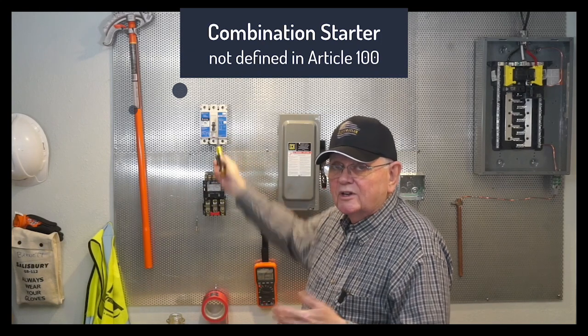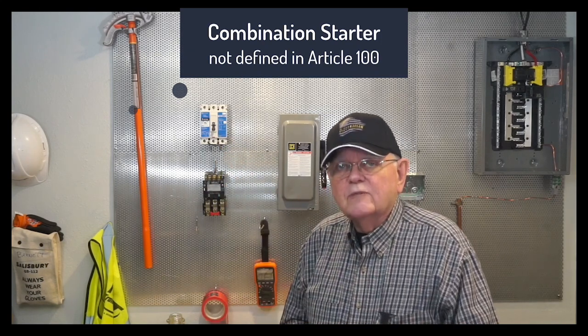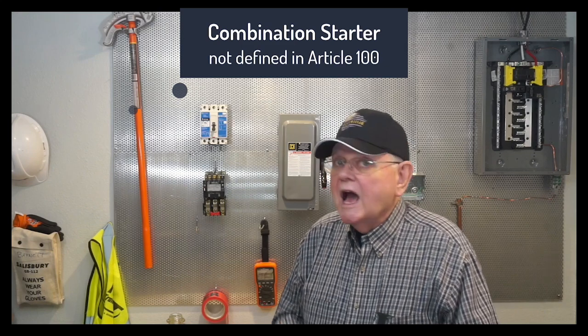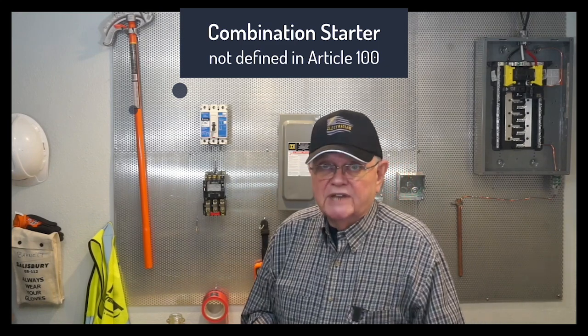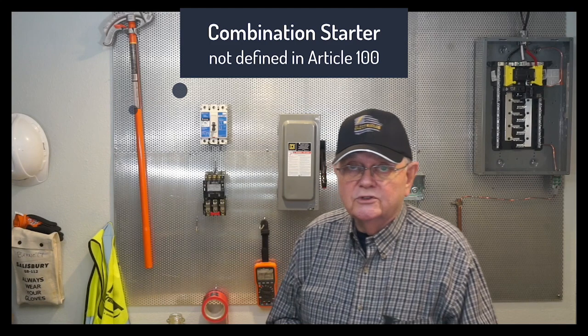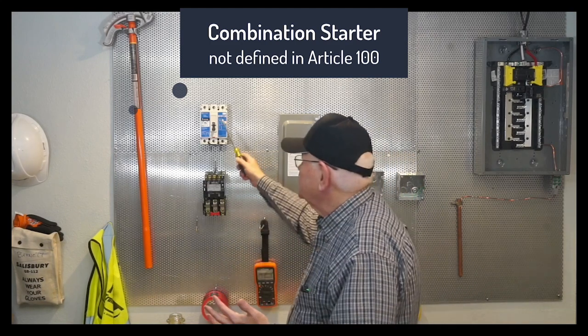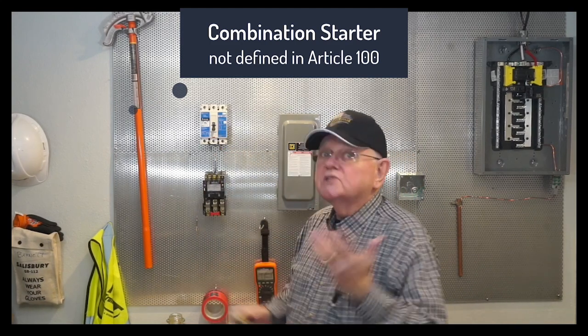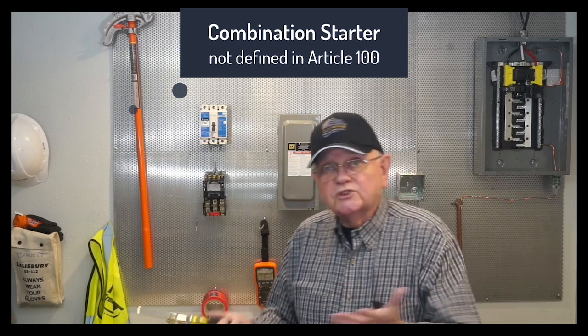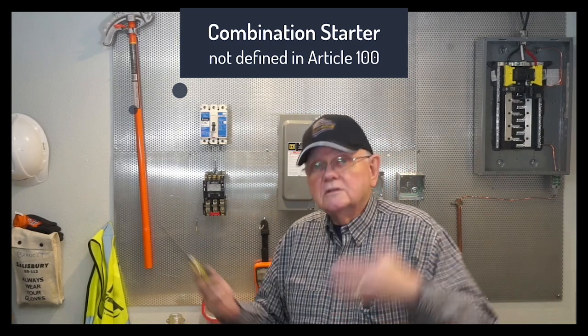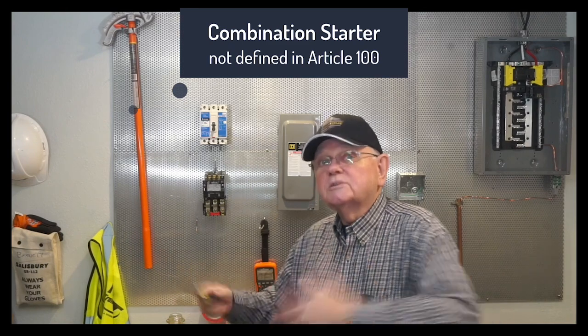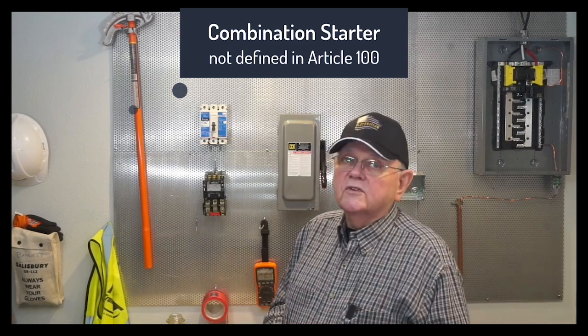So I can open and close the circuit breaker handle. That becomes my disconnect switch. I've got short circuit and ground fault protection. That's requirement number 2. And where is that? Well, that's inside of the circuit breaker. It's an instantaneous trip circuit breaker, short circuit and ground fault protection. A certain large amount of current flow causes the breaker to trip instantaneously then.